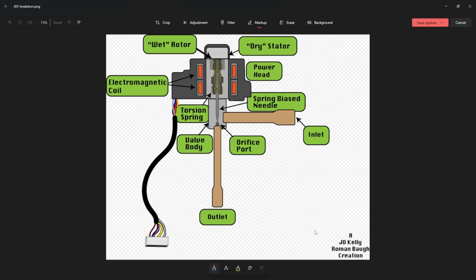So when you say you have a failed EEV, you have to specify if it's the stepper motor or the power head, or if it's the actual valve body. Because a failed valve body and a stepper motor are two completely different repairs. I can tell you, for the 7 years that I've been working on Trane units, I have had to replace one valve body, and I have replaced countless power heads. I can't even count how many that I've replaced.